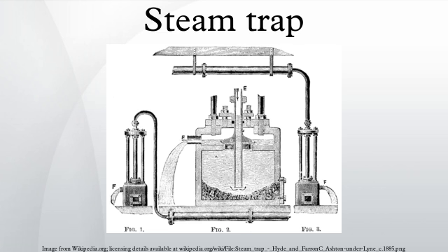Venturi nozzle traps. Venturi nozzle steam traps work by utilizing the basic physics of two-phase flow for the effective removal of condensate from steam systems. Steam and condensate pass through the Venturi nozzle steam traps by a series of staged steps. The denser liquid throttles the Venturi nozzle, which keeps the steam from escaping. Erosive eddy currents are eliminated and any contamination is carried away with the condensate.